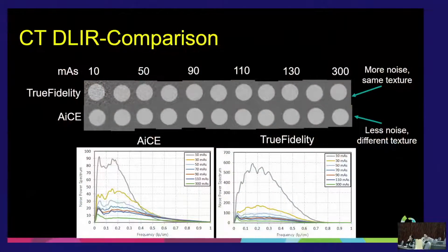So the ACR phantom is limited in the sense that it's just a cylinder. It's one diameter. You can buy annulus rings, so you can insert the ACR phantom and make it a fat phantom. Yeah, we do have. You have those? That's great. Actually, I think I saw a picture of you holding one. So you can do it such that you can mimic different patient sizes. The phantom, as we did talk about yesterday, is not perfect, but it gives you a really good starting point.